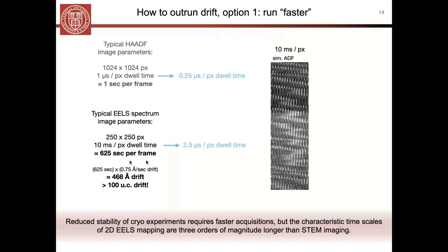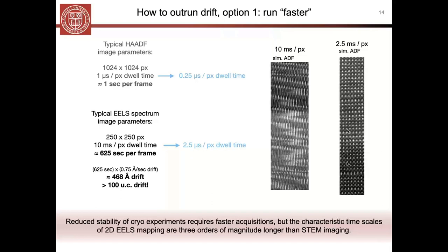If you actually drop this 10 millisecond dwell time down to 2.5 milliseconds, you're going to get an ADF image that looks something like this, again under cryogenic conditions. That 4x improvement from 10 to 2.5 is really starting to get us towards this two-dimensional, spatially localized EELS mapping, which is where we want to go.